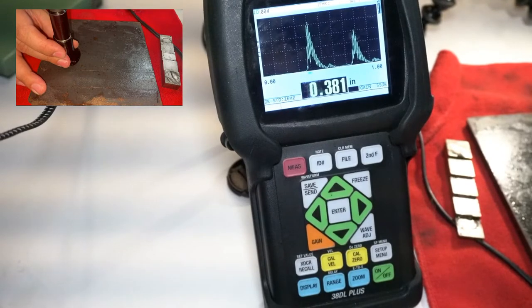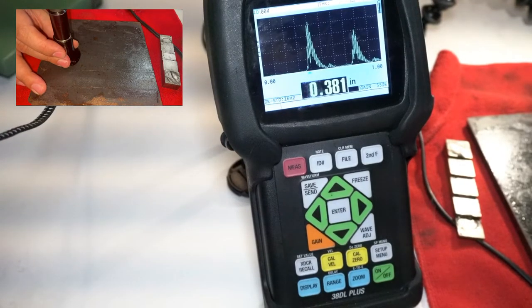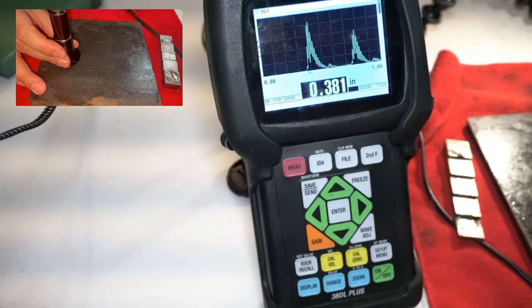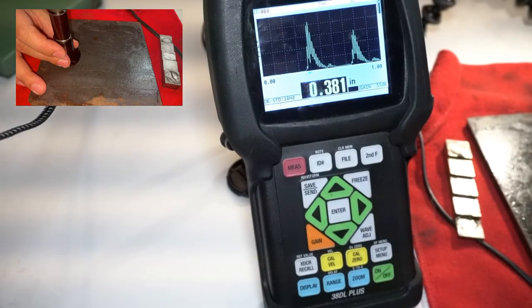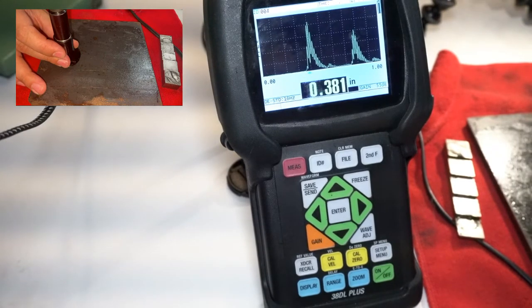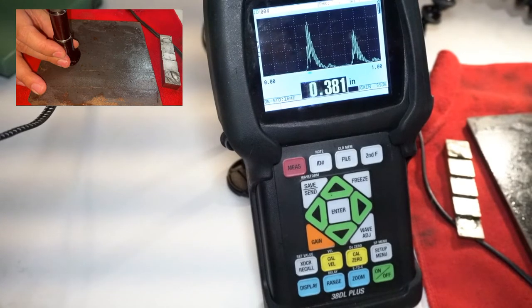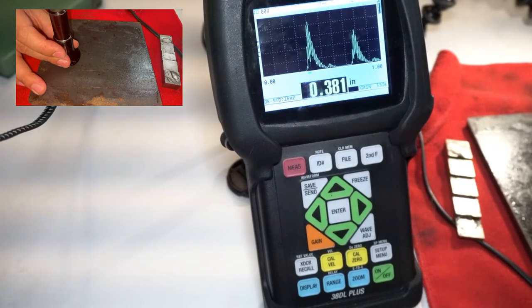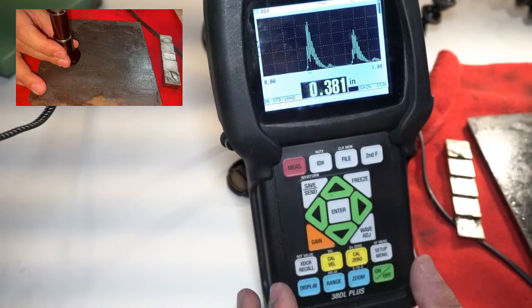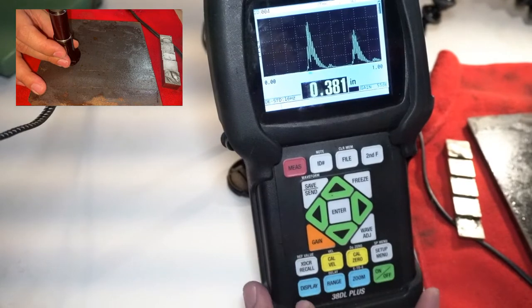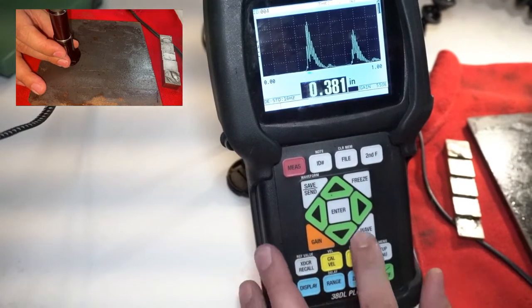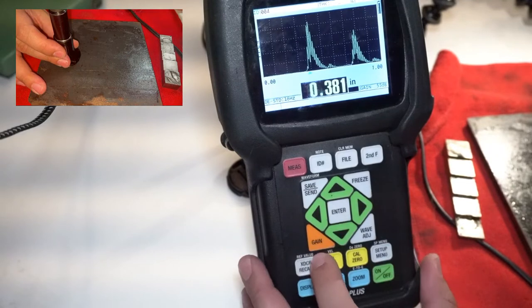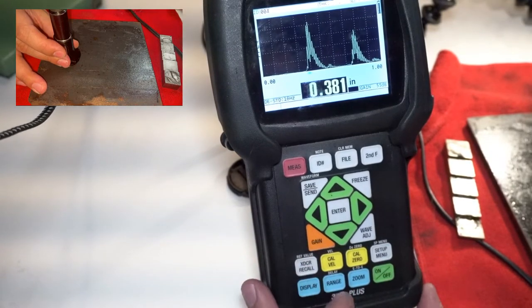Now this measuring rate can be changed. If you're trying to do something with real quick contact, like a high temperature service, you definitely want to move that to max. And if you're trying to find the smallest or the thinnest section in a pitted area, definitely want to go down to about 4 Hertz so you can really watch the signals move. So I'm just going to do a quick demonstration of the difference between max and 4 Hertz.